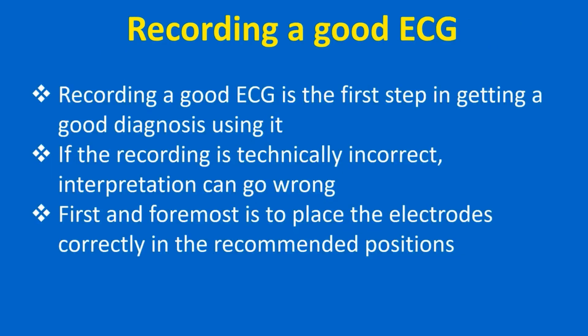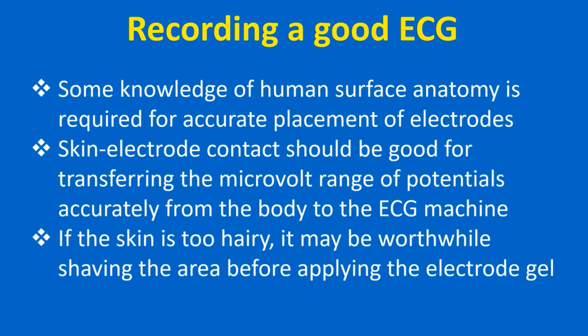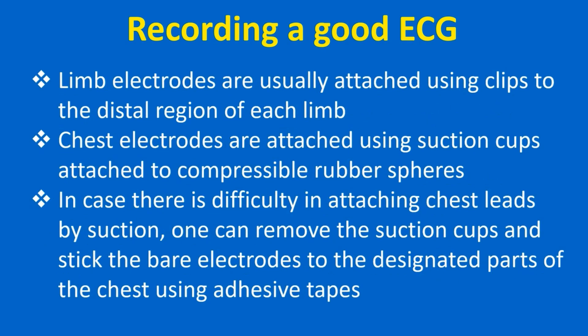Recording a good ECG is the first step in getting a good diagnosis. If the recording is technically incorrect, interpretation can go wrong. First and foremost is to place the electrodes correctly in the recommended positions; some knowledge of human surface anatomy is required for accurate placement. Skin-electrode contact should be good for transferring the microvolt-range potentials accurately. If the skin is too hairy, it may be worthwhile shaving the area before applying electrode gel. Limb electrodes are usually attached using clips to the distal region of each limb, while chest electrodes are attached using suction cups attached to compressible rubber spheres.